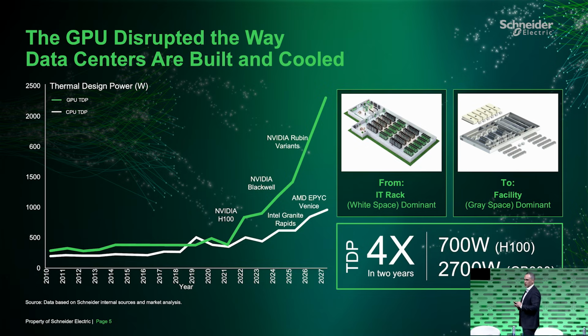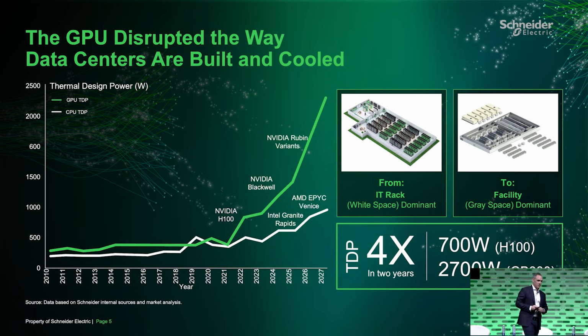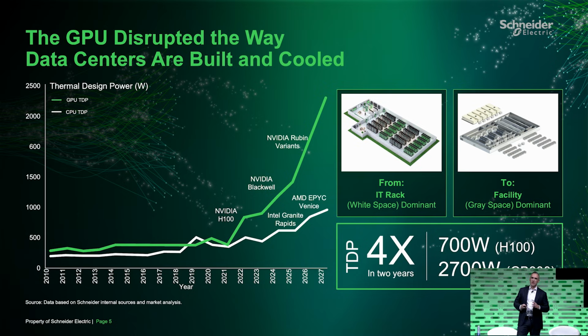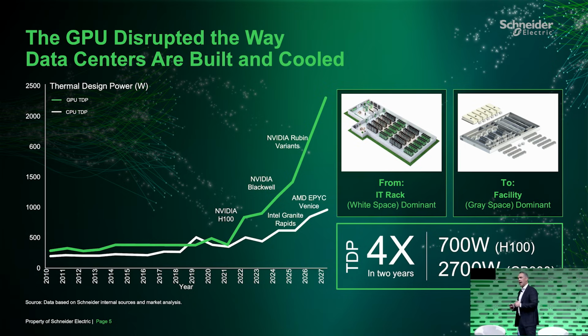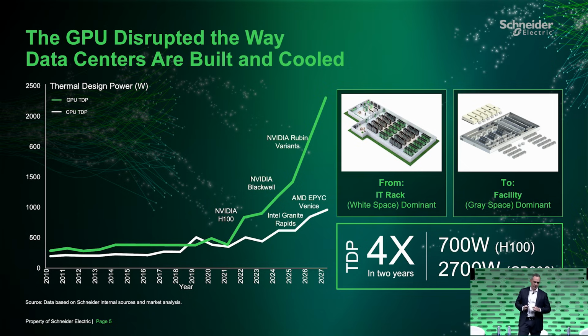And they came up with this chart called a degree of thermal difficulty. That chart, based on those dates, looks exactly like what you're seeing today — almost a vertical wall. So what's happened in the industry is we've got this increasing drive for more power, more processing power out of these chips, and therefore the servers, and that is the demand that pulls from the grid for energy, and that is the demand that's put on your data center from a thermal perspective.